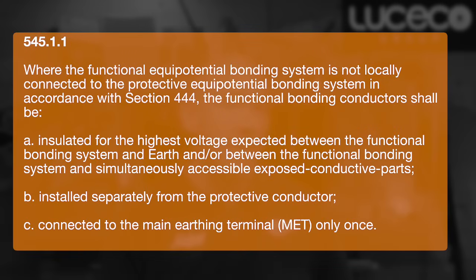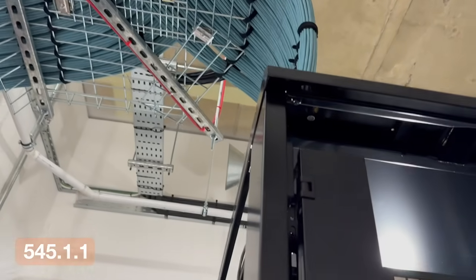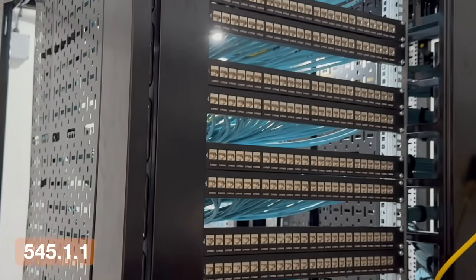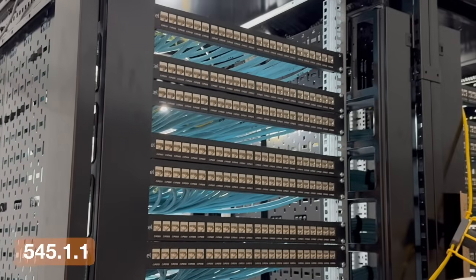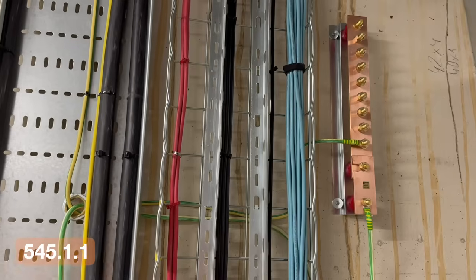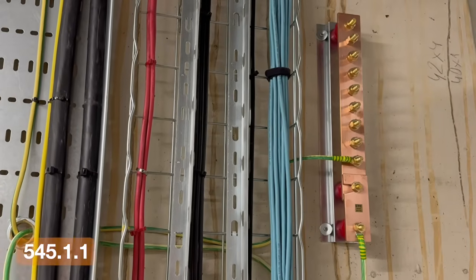Regulation 545.1.1 sets out how a functional bonding system should be arranged. Functional bonding conductors must be insulated. They must be installed separately from protective conductors, and they must only be connected to the main earthing terminal at one point. That is important. Keeping them separate prevents interference between systems. Insulating them recognises that they may carry current during normal operation, and having a single connection point avoids circulating currents.